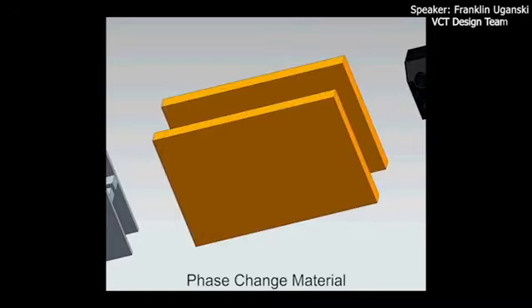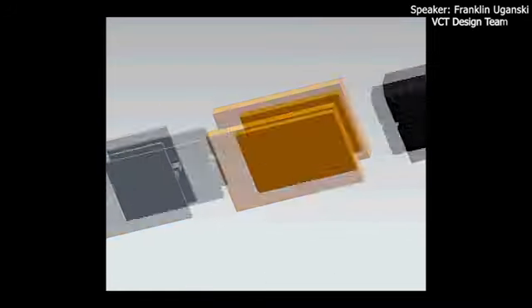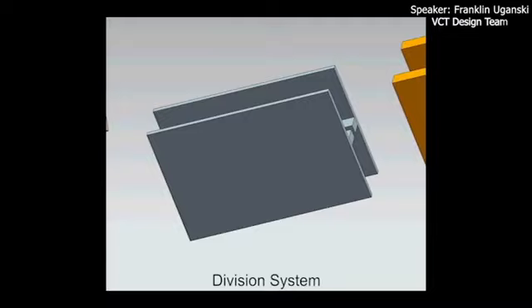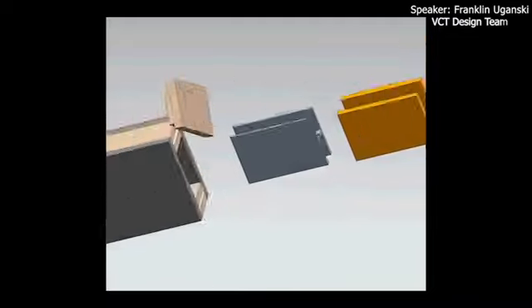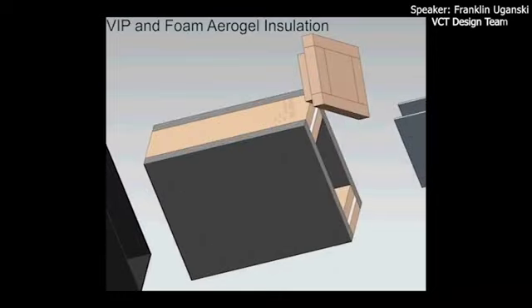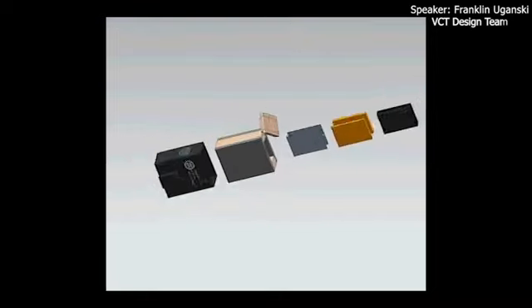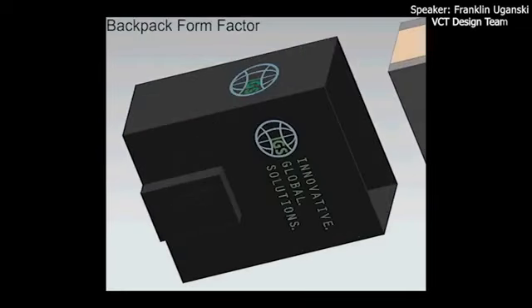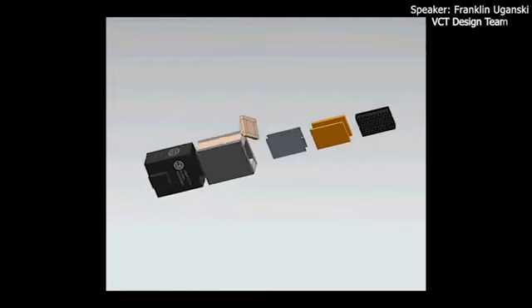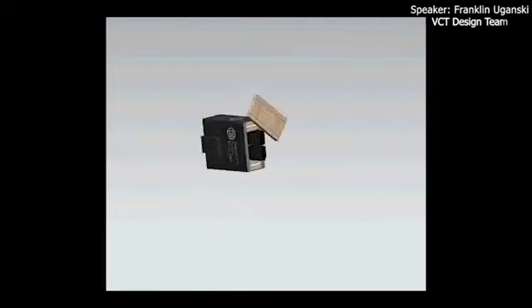The removable phase change material provides cooling in a specific temperature range. The internal division system compartmentalizes components and provides structure for the onboard temperature monitoring system. The combination of vacuum insulated panels and foam aerogel provide the insulative properties necessary to reach the holdover time requirement. Additionally, a backpack form factor makes the unit easily transportable on foot or by motorcycle.